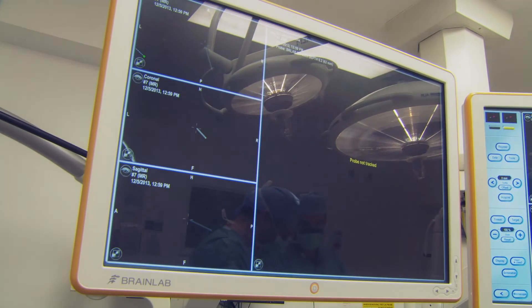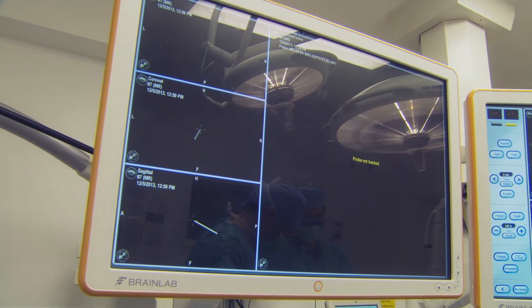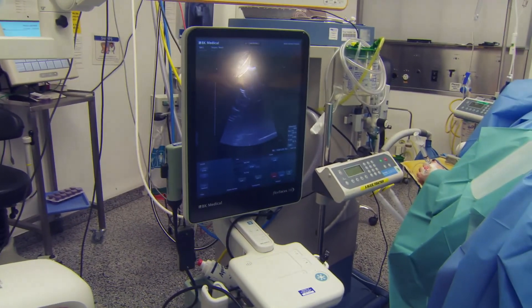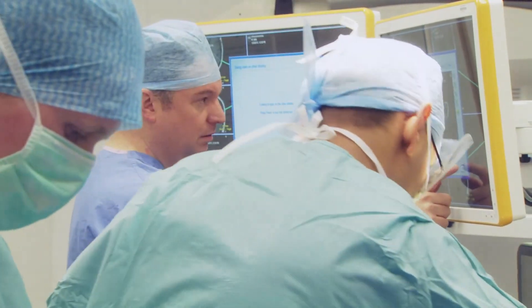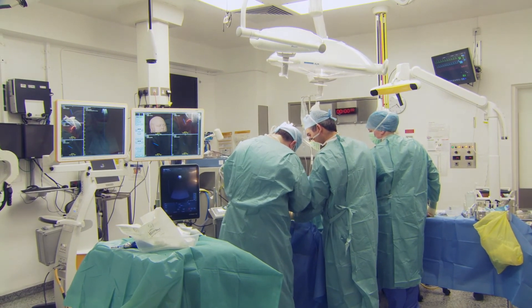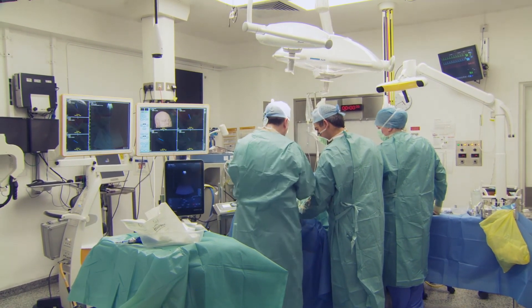The advantage of the BK system is that it's easy to set up. We've got two specific cranial probes and the resolution and screen images are excellent. It's very easy to adjust in theatre and our staff are comfortable with those adjustments. It's also a nice portable design — it fits into a small, crowded neurosurgical theatre very well.